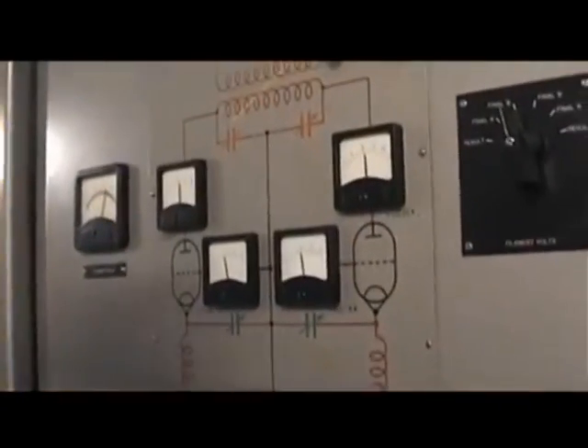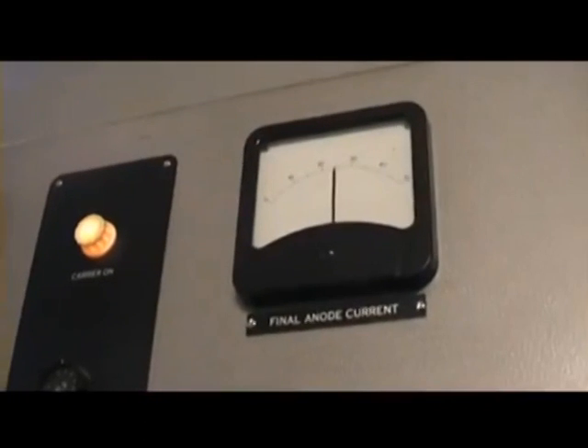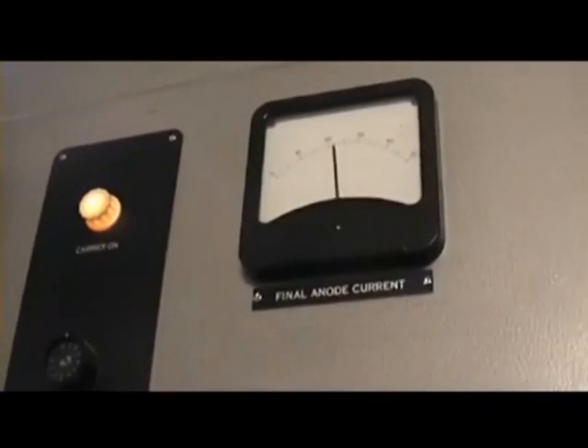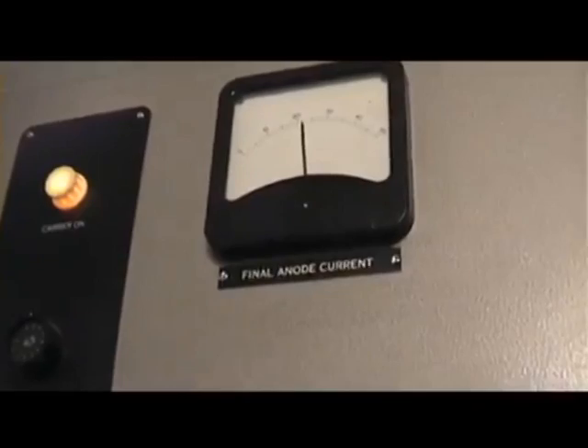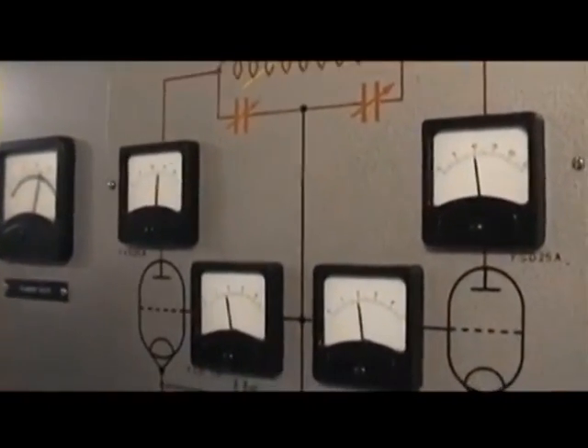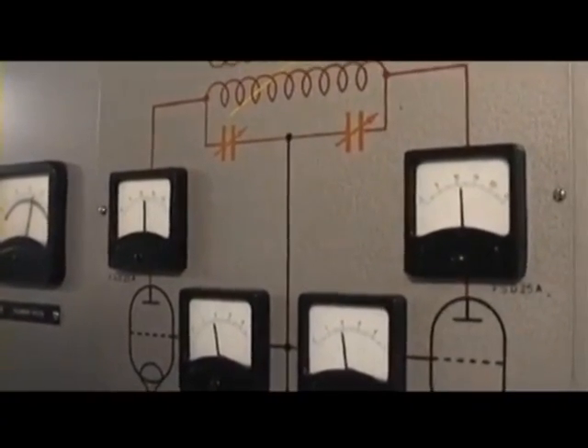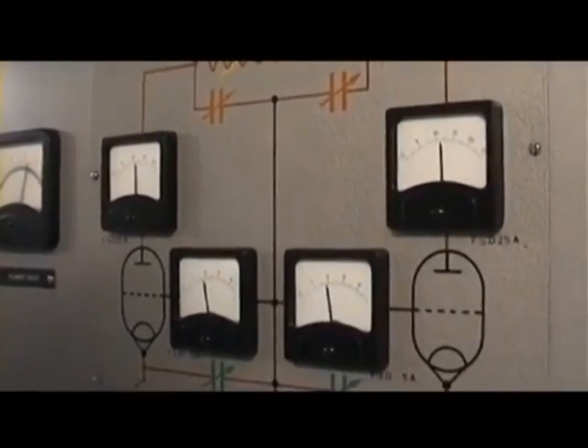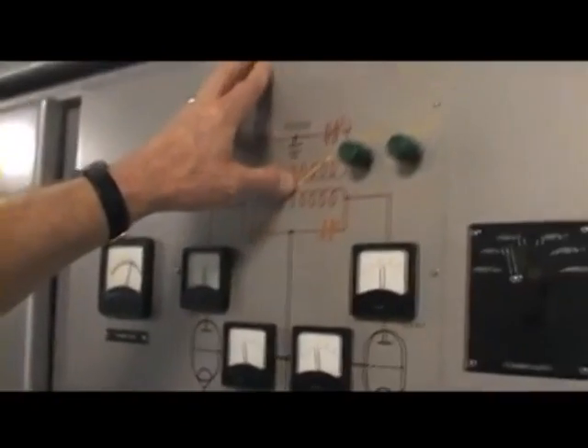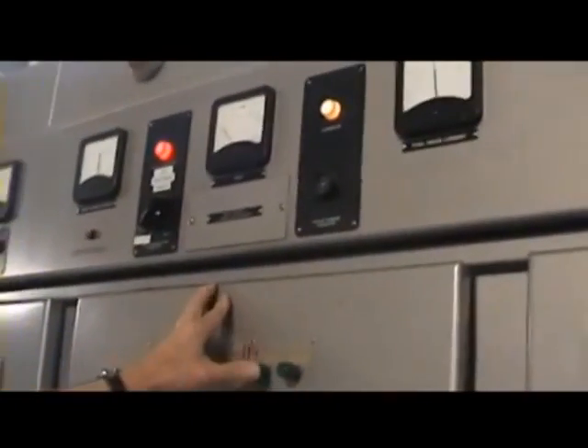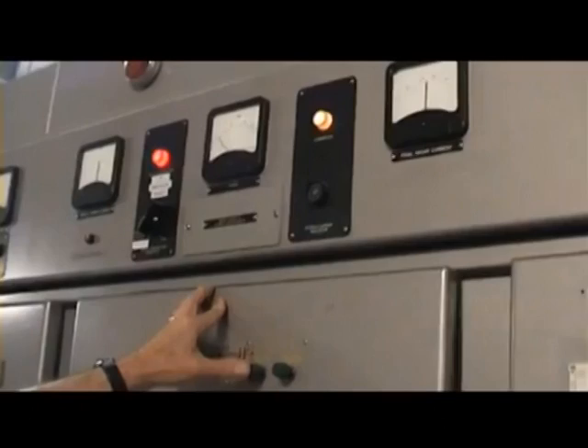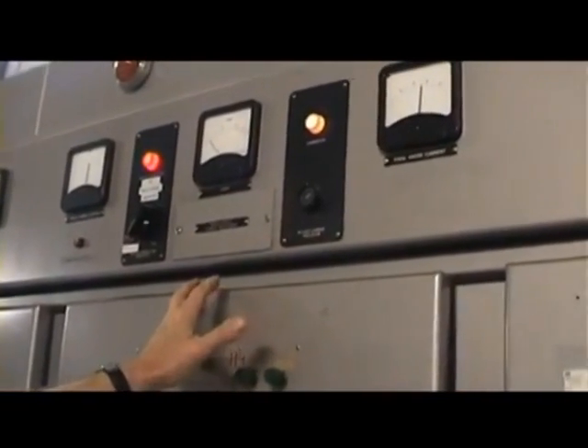Grid's balanced, good. Look at the finals. Hands move down, eye moves to this meter combined. There we are, just dip at 22 amps. Look at the final stage here and set them both for the same value, just over there. So that's 22 amps, it's about 220 kilowatts. Want to run a bit more power, 250, just couple up to 26 amps. 26 amps, 250 kilowatts.